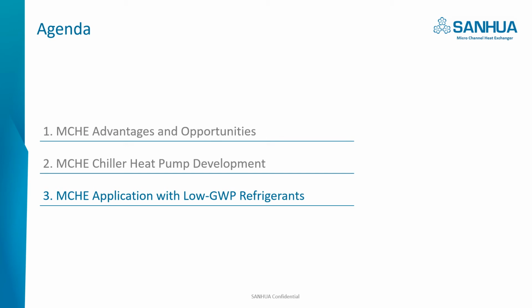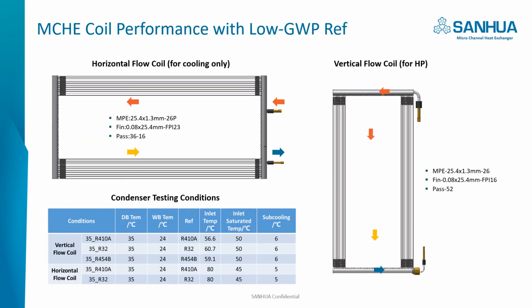So the third part is about microchannel application with low GWP refrigerants. Because the microchannel heat exchanger can fully utilize the charge advantage for the low GWP flammable refrigerants, the industry is thinking about redesigning the system using microchannel. But the first question would be, how would microchannel perform with the low GWP refrigerant transition?